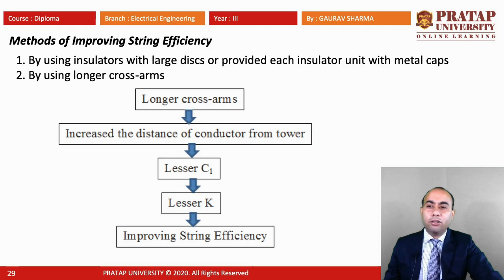And second is by using a large cross arm. When we use a long cross arm, the distance of the conductor from the tower is increased, so C1 is less, K is lesser, and this improves our string efficiency. But when we use a longer cross arm, our overall tower structure has to be increased, so our overall capital cost also increases. So it is also not economically viable.